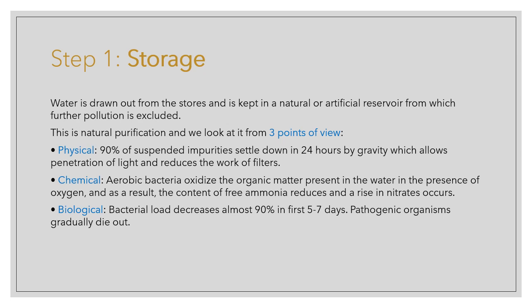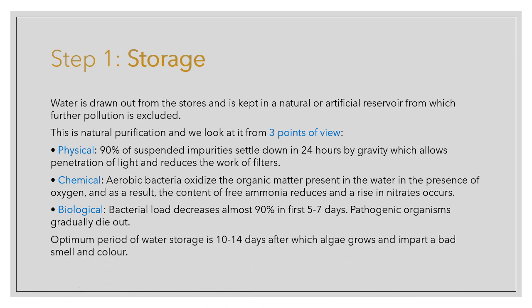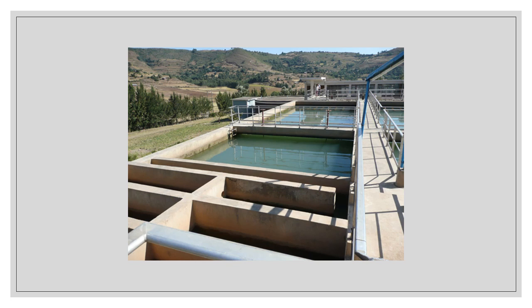So what would be the optimum amount of time that we should store water? Well, it's about 10 to 14 days, because after that, the algae starts to grow and this would impart a bad smell and color to the water. Here is an example of what a storage site looks like. With this, we'll move on to the next step in the purification process, which is filtration.